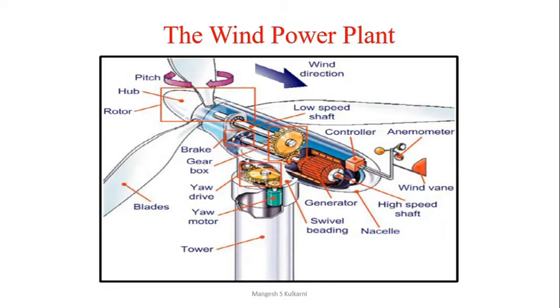When output reaches the maximum power the machinery is designed for, the wind turbine controls govern the output to the rated power. The wind speed at which rated power is reached is called the rated wind speed of the turbine and is usually a strong wind of about 15 meters per second.